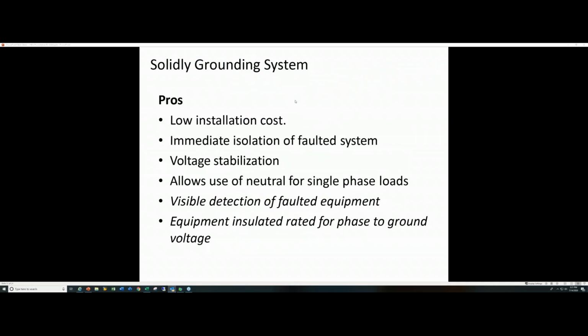Well, a solidly grounded system has a low installation cost and immediate isolation of a faulted system, but the caveat there is, A, everything's properly coordinated, and you've done your due diligence by doing your maintenance on your breakers, and you're coordinated properly, and you're not overreaching when the fault happens and taking down more of your system than needs to be. It does provide for voltage stabilization across the network.